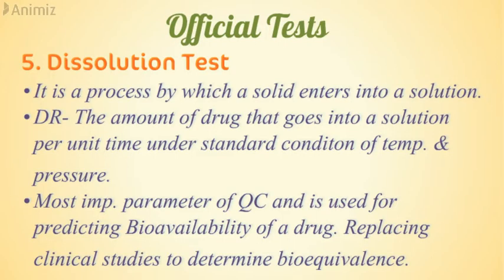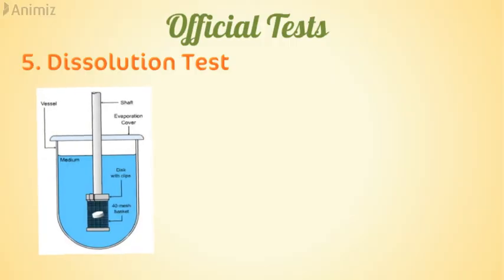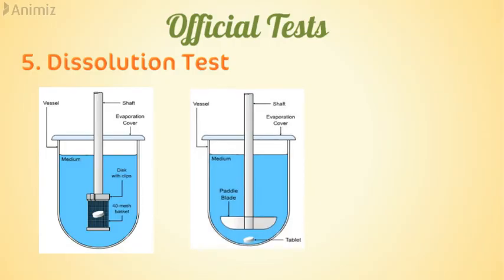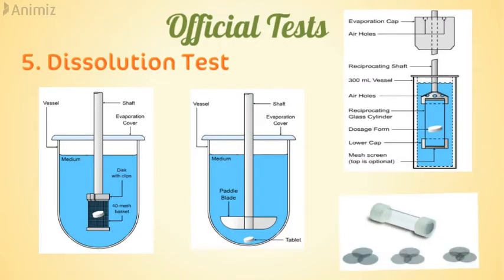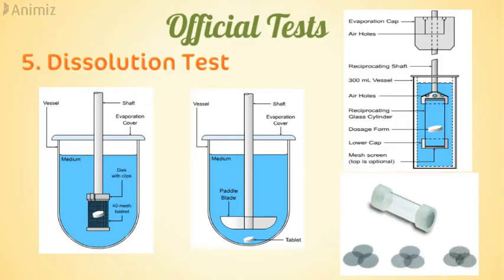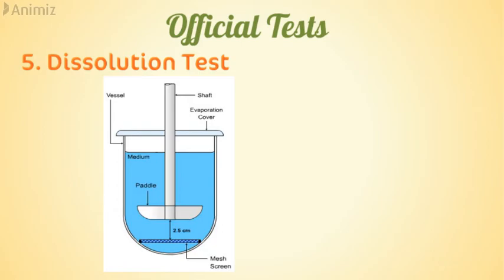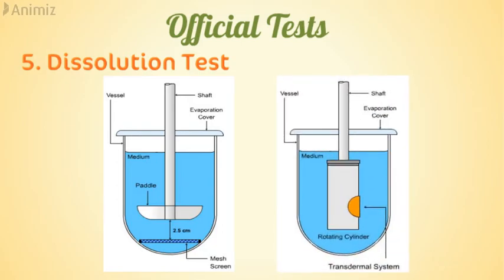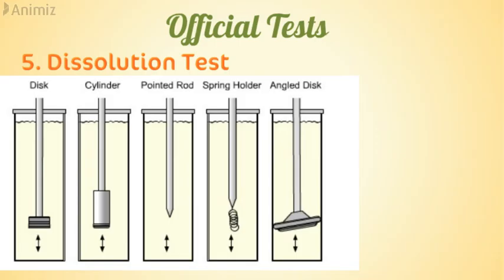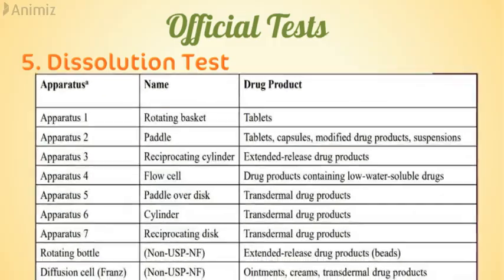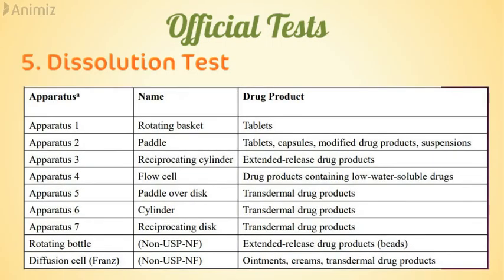Different dissolution apparatuses include USP Apparatus 1 (rotating basket), USP Apparatus 2 (rotating paddle), and USP Apparatus 3 (reciprocating cylinder). Different dissolution tests are used depending on the dosage form and the physicochemical properties of the drug.